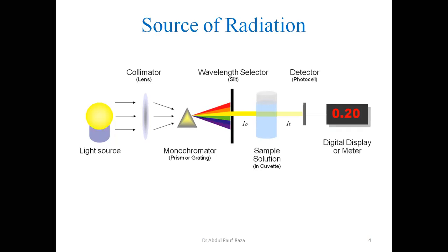If we are selecting the whole range, then keep in mind the D2 lamp has a limited life. You cannot just go to the market and purchase a deuterium lamp. No, not at all. It is very expensive. It costs more than 100,000 rupees. So its life is also not very high. It has almost 300 to 400 hours of running. So if we make unnecessary use of UV light, then it shall be wasted.